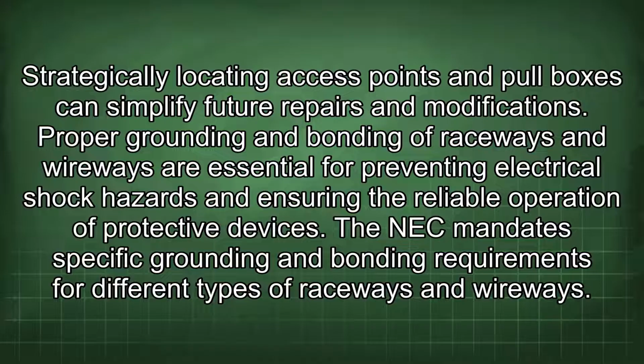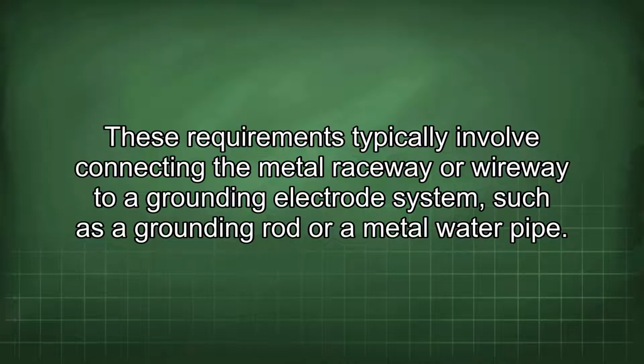Proper grounding and bonding of raceways and wireways are essential for preventing electrical shock hazards and ensuring the reliable operation of protective devices. The NEC mandates specific grounding and bonding requirements for different types of raceways and wireways. These requirements typically involve connecting the metal raceway or wireway to a grounding electrode system such as a grounding rod or a metal water pipe.